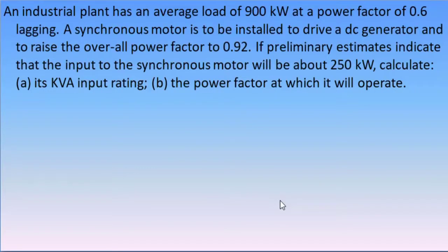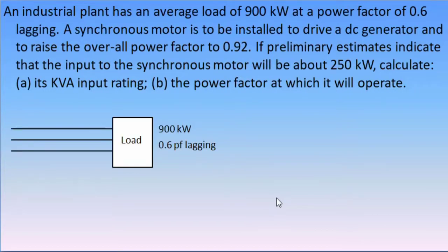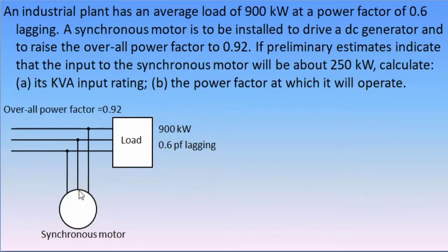Let's review and understand the problem. The average load for the plant is 900 kilowatts at a power factor of 0.6 lagging. A synchronous motor is to be installed to drive a DC generator and at the same time to increase or raise the overall power factor to 0.92.